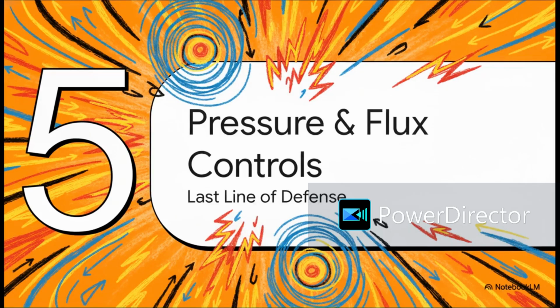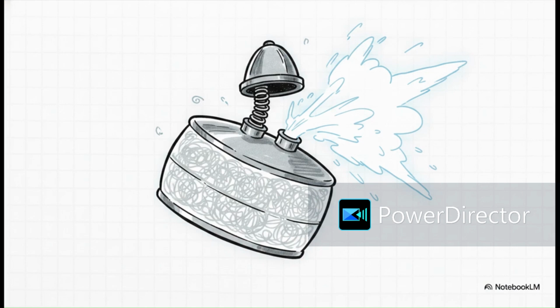Finally, Section 5, Pressure and Flux Controls, the last line of defense. These are your extreme physical failsafes, the last thing standing before the transformer literally destroys itself. First up is the PRV, the pressure relief valve. When really serious faults happen, the oil inside vaporizes instantly. That creates crazy, dangerous internal pressure inside a sealed metal tank. If that pressure has nowhere to go, the tank ruptures.